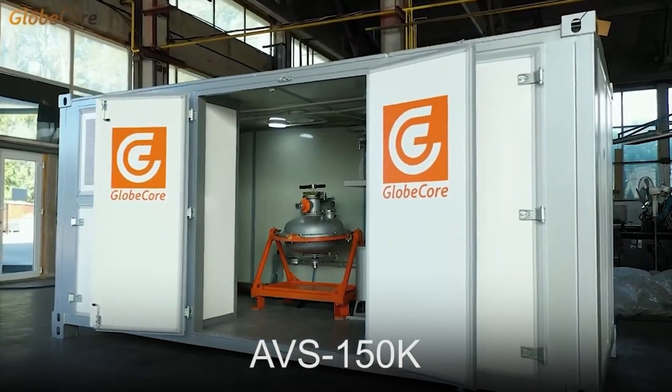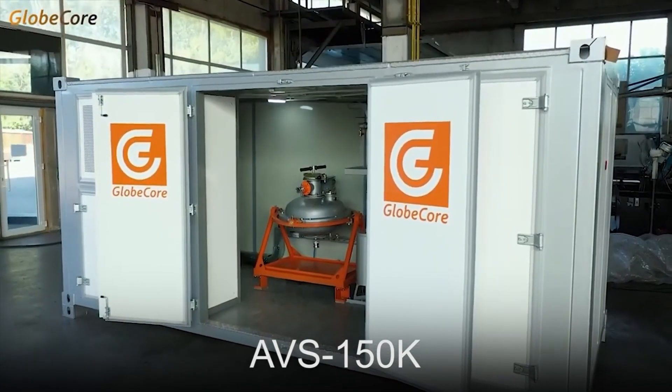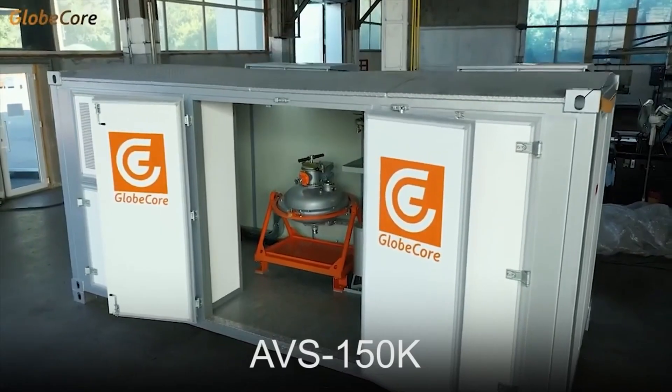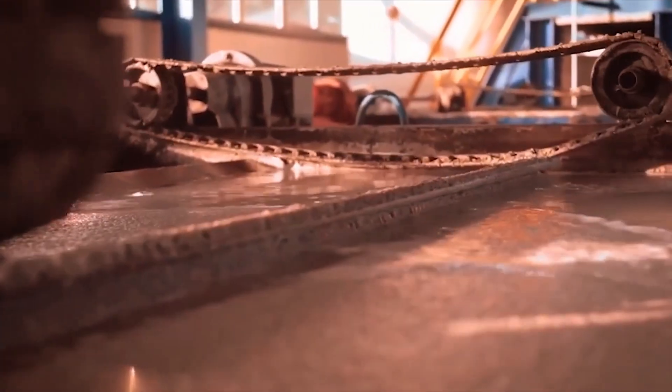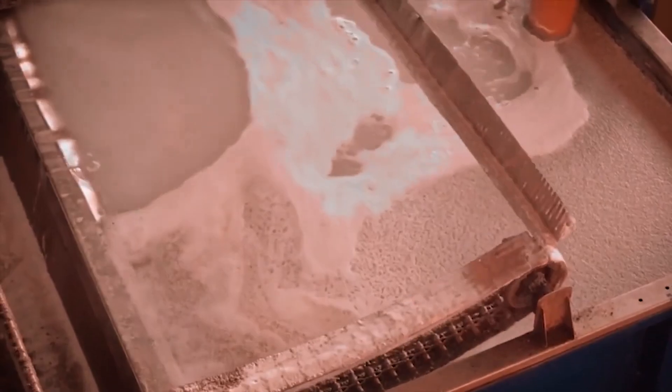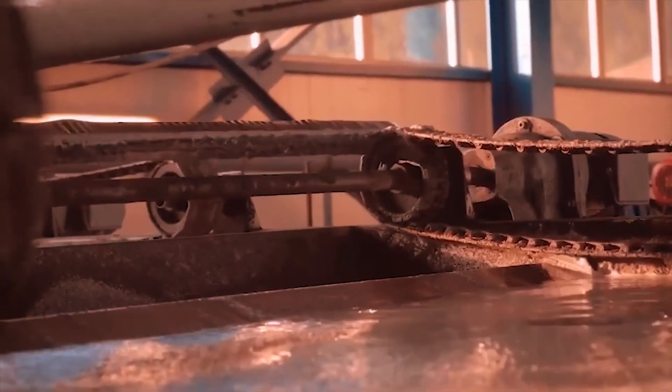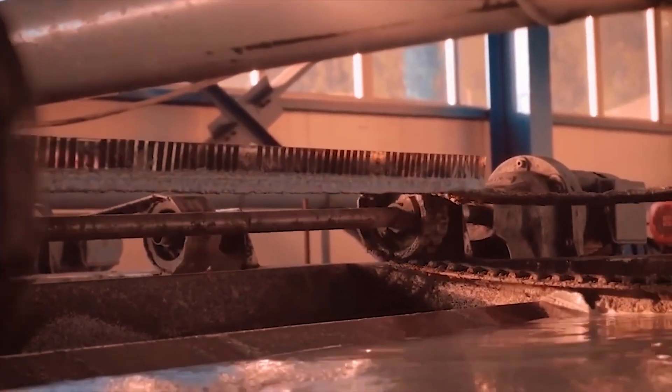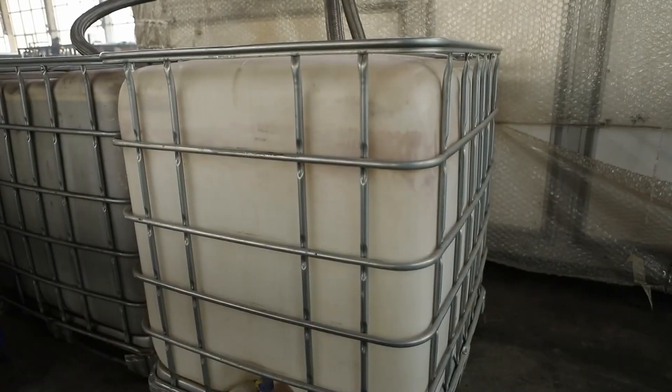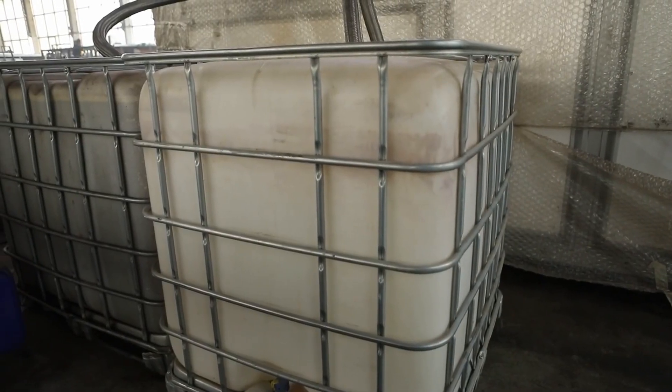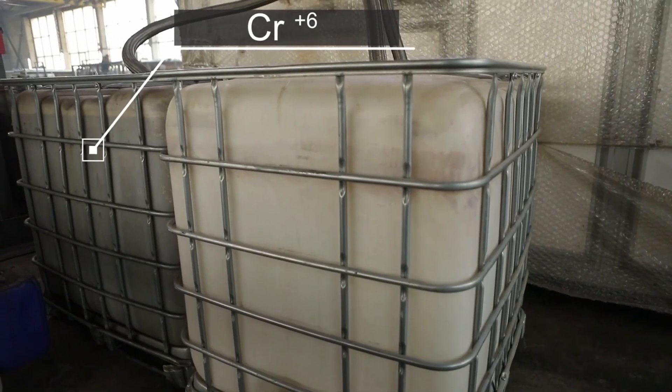Let us discuss how these processes are implemented in GlobeCore AVS-150K mobile complex. Wastewater may come from different workshops and contain chromium of various concentrations. In this case, it is difficult to correctly calculate the amount of chemical agent. Therefore, during the work shift, all the effluents are collected into a separate balancing tank where the concentration is equalized.